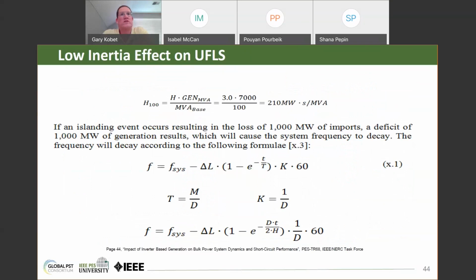Another area, the next slide, starts into the effect on under frequency load shedding, and this is an equation that can be used to estimate the rate of change of frequency in an area. So if I have an area that has 1,000 megawatts of import, and I'll show you what the system actually looks like in just a second. For the example here, it's an 8,000 megawatt system with 7,000 megawatts of generation and 1,000 megawatts of import. The loss of that 1,000 megawatts of imports is going to cause a rate of change of frequency on the initial trip, and until the governors can respond, there is a danger of under-frequency load shed in the area.